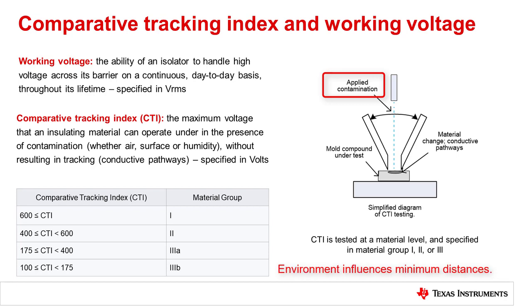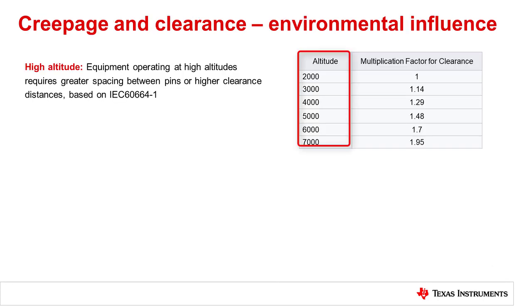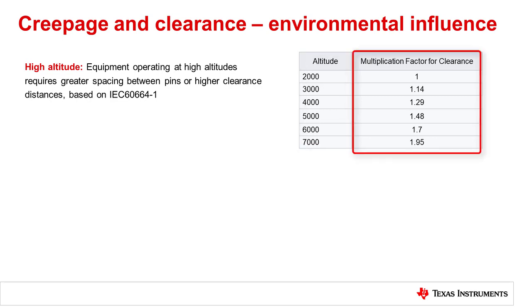Environmental conditions will also influence minimum creepage and clearance distances, with dependence on the end equipment use case, altitude, and environmental pollution degree. At higher altitudes of 2,000 to 5,000 meters above sea level, the air pressure is lower, causing peak overvoltages such as surge or temporary overvoltage to more readily cause arcing between isolator pins. Equipment operating at high altitudes require greater spacing between pins or higher clearance distances based on IEC 60664-1, which provides multiplication factors by which clearance must be increased at higher altitudes in order to protect from altitude-induced arcing.